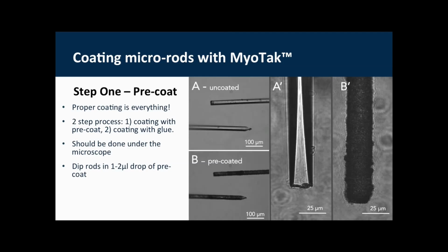So when dipping in pre-coat, you dip for about 10 to 30 seconds at a time, then take the rods out and check the rods for a uniform coating like you see on the low magnification and high magnification images here. When the desired pre-coat is reached, the rod should then be allowed to air dry, ideally for 30 minutes or more. Otherwise, some pre-coat can slough off in solution.